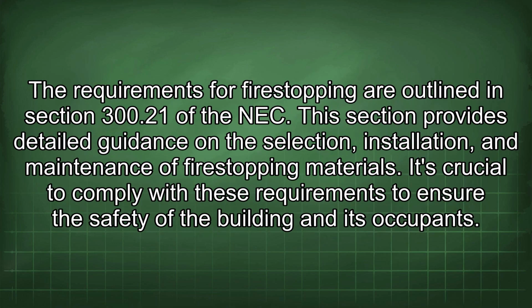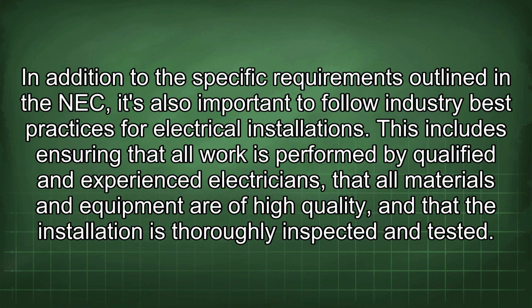The requirements for fire stopping are outlined in section 300.21 of the NEC. This section provides detailed guidance on the selection, installation, and maintenance of fire stopping materials. It's crucial to comply with these requirements to ensure the safety of the building and its occupants. In addition to the specific requirements outlined in the NEC, it's also important to follow industry best practices for electrical installations. This includes ensuring that all work is performed by qualified and experienced electricians, that all materials and equipment are of high quality, and that the installation is thoroughly inspected and tested.